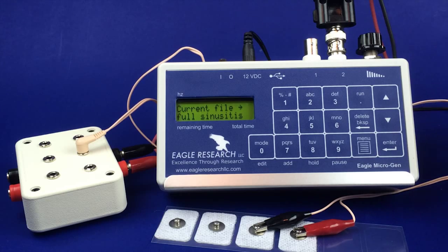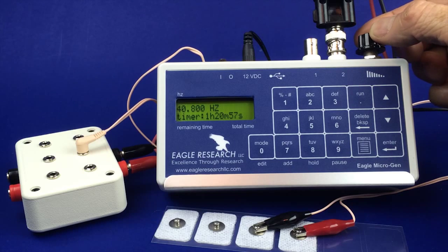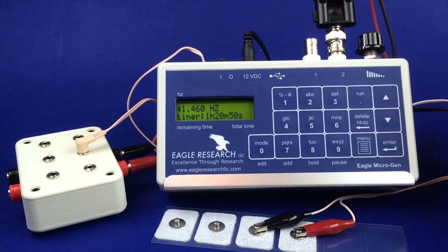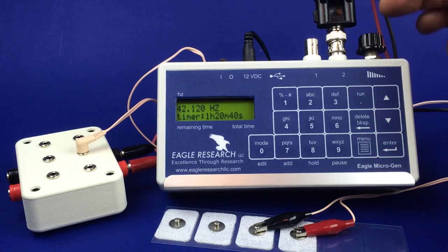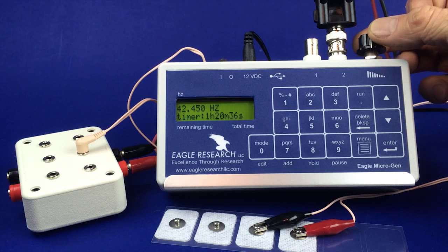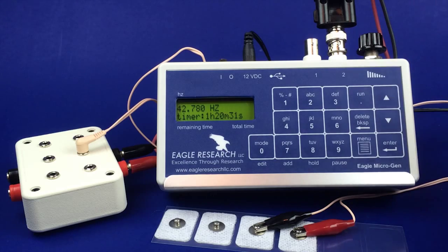Again, pointing out, make sure that this dial is all the way down, hit the Run button, and then turn the dial up slowly until you begin to feel the current, and then just back it off a little bit. Most practitioners will recommend that as the main way to have it set at the right intensity. Again, when you turn it on, have it in the low intensity all the way down. Once it's on, turn it up slowly until you begin to feel the current, and then back it off a little bit.